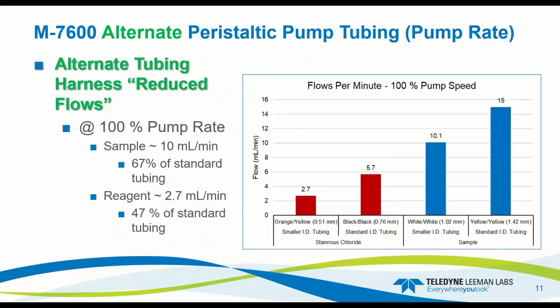So once we got in here and looked at how this pump tubing worked, it actually reduced the sample size by 33%. So we're using 67% of what we would if we were running with the normal pump tubing. But the biggest savings is on the reagent side. We were using 47% of what we would be with standard tubing. So that's a 53% reduction in stannous chloride, and stannous chloride is relatively expensive. So that's where the green chemistry comes in for us: the reduction in reagent and reagent costs.